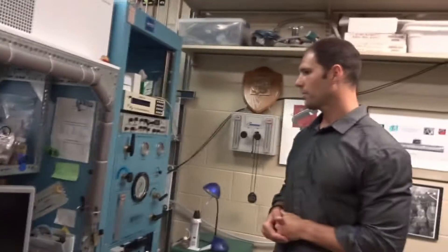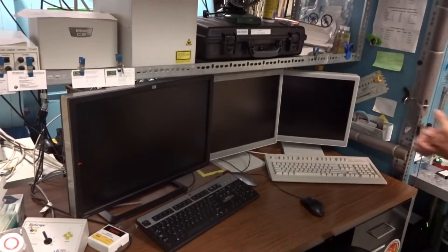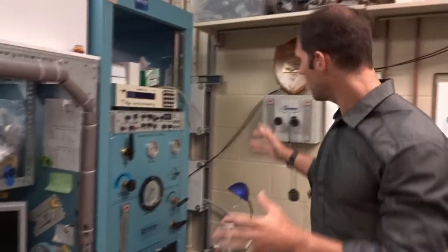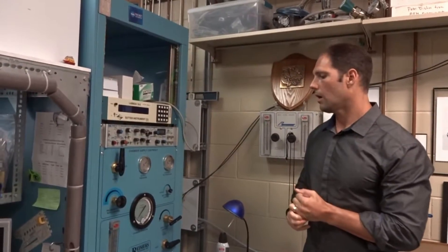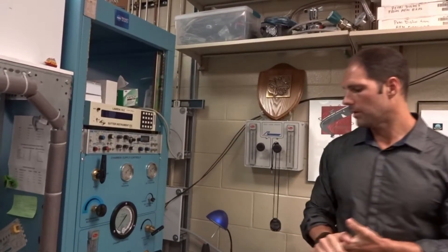I thought maybe I'd just strap it to your back, but I got about a dozen people pushing it. This is the control station. We could do confocal microscopy and electron microscopy on here. We also had an electrical stimulator so it could stimulate the cells. This unit here basically controls all the gas tanks on the other side of the wall — we call that the gas farm. Depending on what experiment we were going to run, I could turn on the nitrogen, the oxygen, specialty mixtures, helium even, and pressurize the chamber. I could set the flow of the pressurization or the decompression based on some of the controls here.